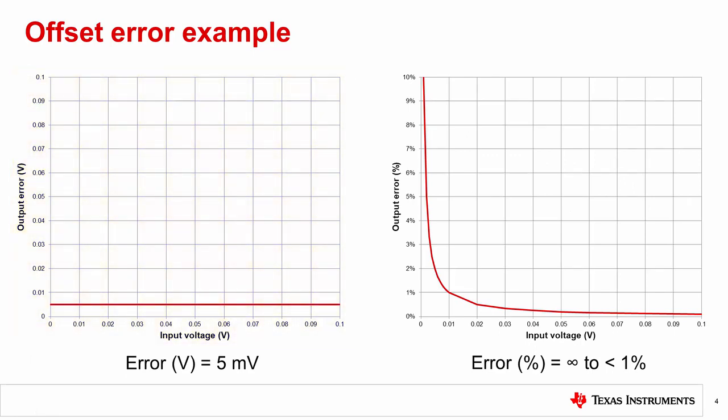The plot on the left shows the output error in volts between the actual and ideal outputs, which is a constant 5 millivolts across the entire input range of 0 to 100 millivolts. Calculating the percent error gives us a much different result. The error becomes large at 0 input voltage, since the error voltage of 5 millivolts is large compared to the ideal output of 0 volts. The error drops significantly with larger input levels, dropping to less than 1% at 10 millivolts of input signal. Designing for a specific operating region can help mitigate these offset errors. Maintaining an input voltage which is significantly larger than the input offset voltage reduces the effect of the input offset voltage on the measurement.